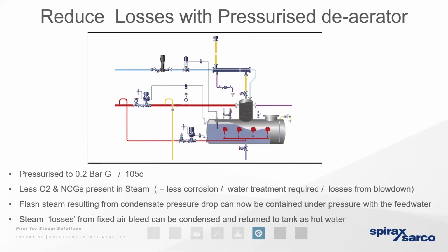For three, we're consuming less energy. If we're putting water into the boiler at 105 degrees, compared to 85 degrees in a traditional hot well, we need to consume less energy to raise steam again. The steam tables tell us that. Point four, there's going to be less air and other non-condensable gases entrained within the water at a higher temperature compared to at a lower temperature. Remember, the lower the water temperature, the more gas there is contained within it, and that brings us on to point five. If we've got less oxygen and non-condensable gases in the water at a higher temperature, we need to add fewer chemicals to polish off that last remaining mass of gas.